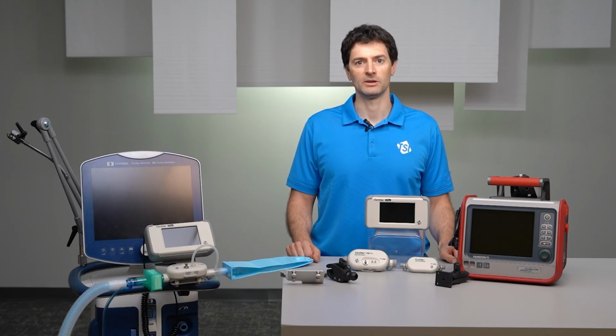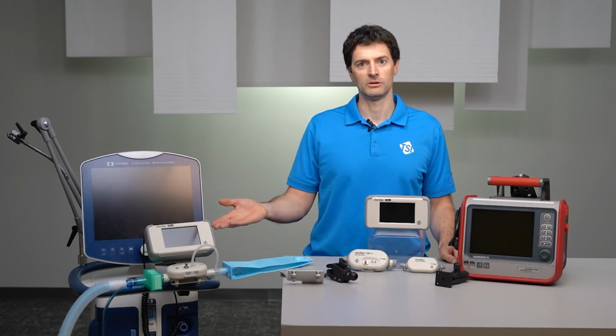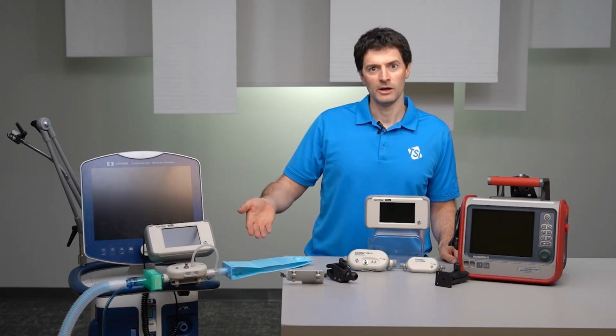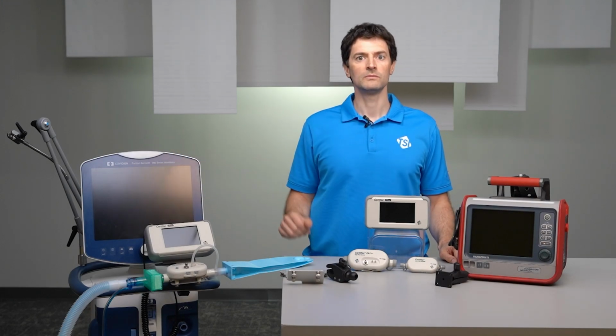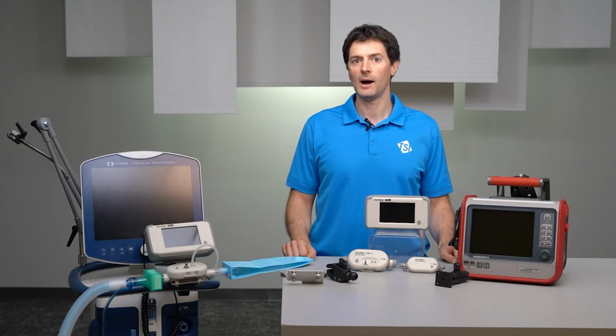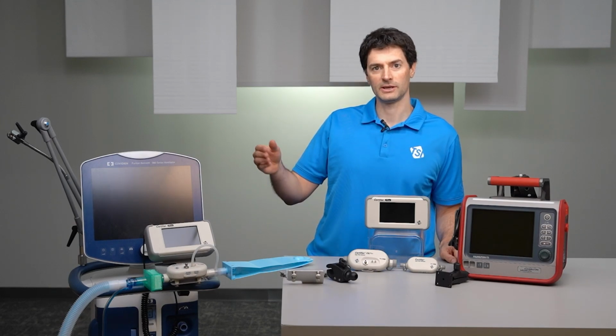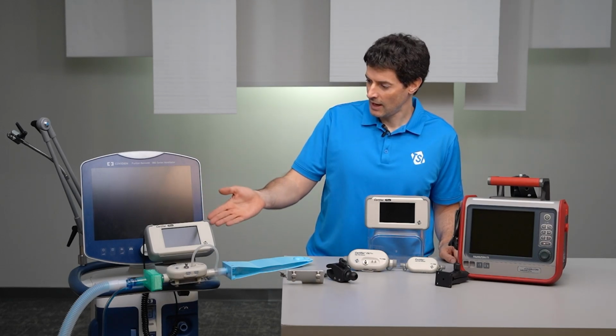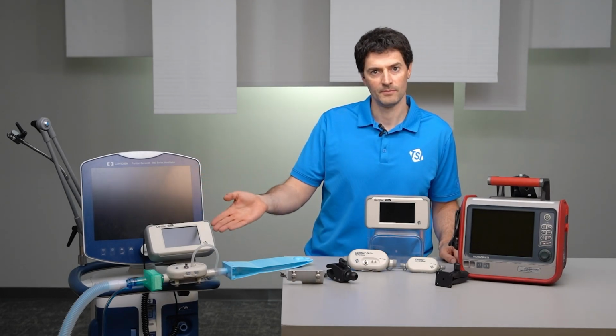The mounting system is strong enough to hold the entire test setup of the certifier, test lung, and tubing. And mounting also helps to optimize the positioning of your test instrument, making it easier for you to quickly compare readings between the ventilator and the flow analyzer.